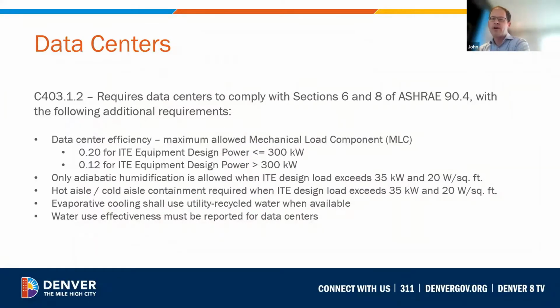The code also has a new requirement that's just a reporting requirement: to report water use effectiveness, that is, the water consumption for these data centers. As is common procedure, hot aisle, cold aisle containment is required for most data centers to be able to effectively reject the heat and not have the heated air in close proximity to the actual servers.